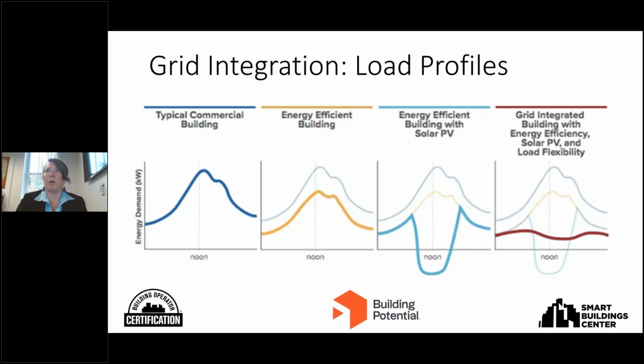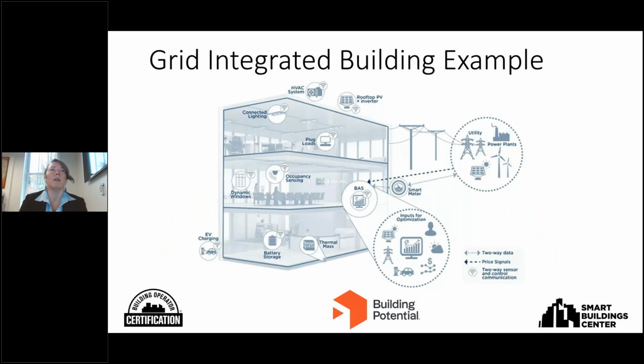Just another quick look at a grid integrated building. You can see there's integration within the building itself with connected lighting, HVAC, possibly all using the same occupancy sensors. This building is operated by a building automation system with various inputs and two-way data flow from the utility to the building and back, so that building can provide those load flexibility services. We're seeing this definitely in new buildings, but also in implementations in existing buildings, and I'll show an interesting case study in a little bit that demonstrates that.